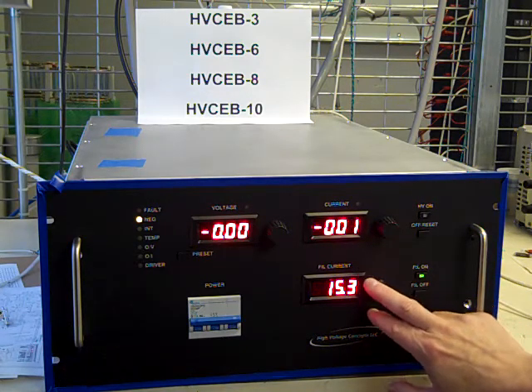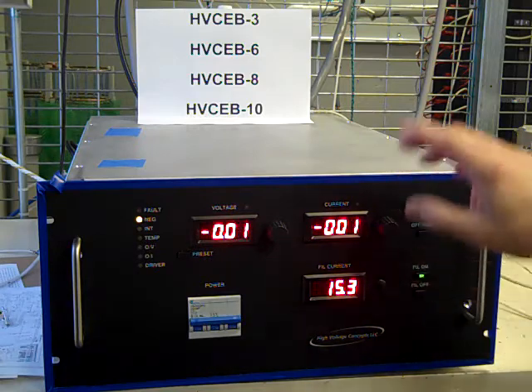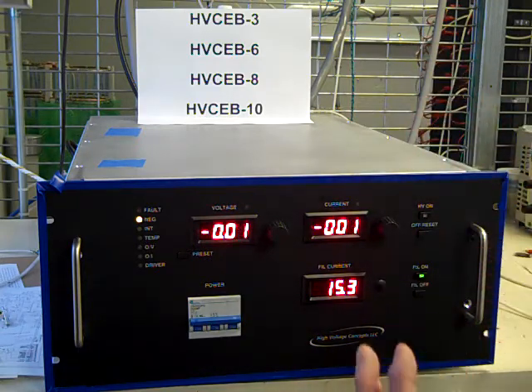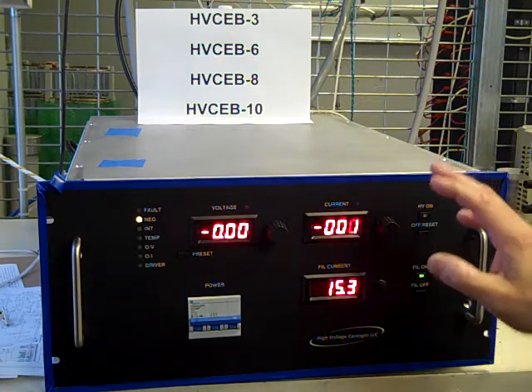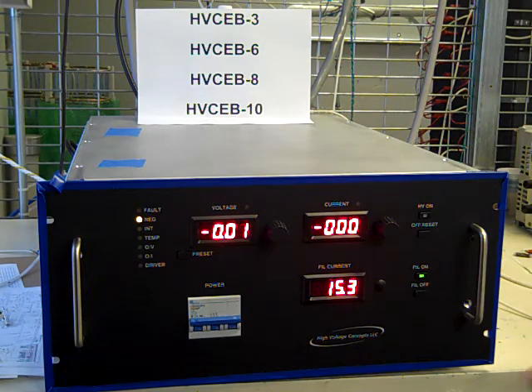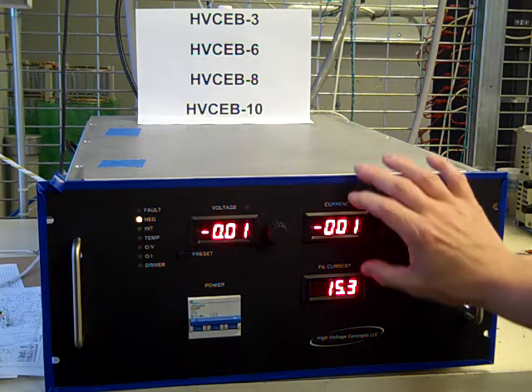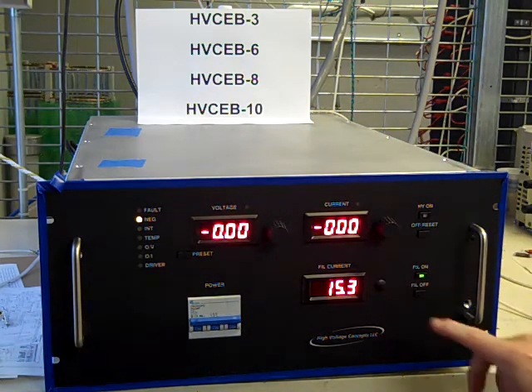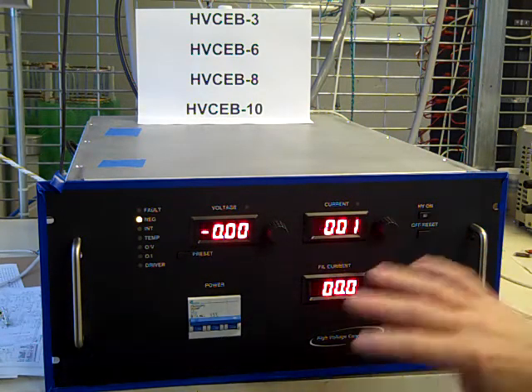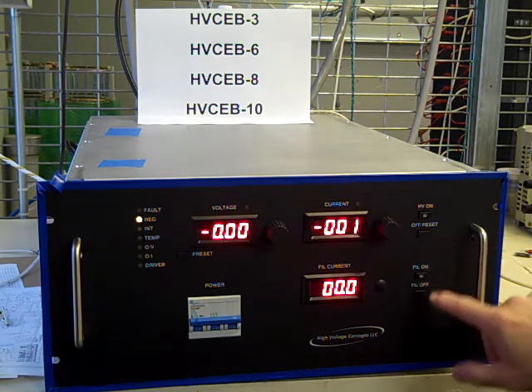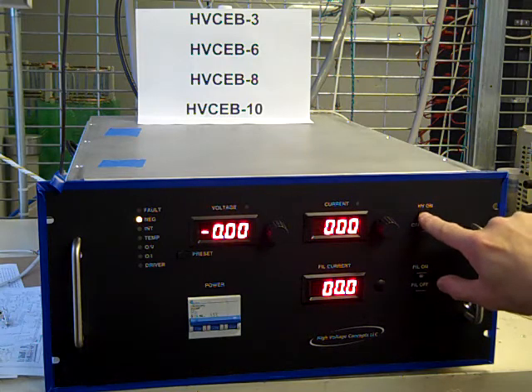This value is approximately set for about 10 amps on the 3 kilowatt because the filament is a little bit lighter. We set it at around 15 on the 6, and on the 8s we set it around 20-22 amps. These are all just below the dark region where you have enough heat so that you don't thermally shock the filament, but yet you're not emitting any electrons because you're still in that dark zone. But yet you're very close to the operating point of a very low current set point. Okay, so in this case, we would be ready to turn high voltage on. And as you can see, if I don't turn on the filament and I try to turn high voltage on, nothing happens.